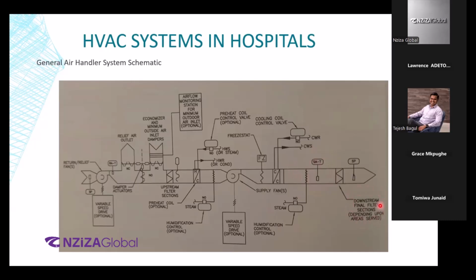These filters will be the same filters that we spoke about, the minimum filtration efficiency required, right? There might be more filters coming into it as well as over here at the outdoor air stream, because we don't want outdoor air to directly come into the air handling unit. If there are minute particles that might cause failure in the stream up over here or over here. So that's why we have this upstream filter section over here.